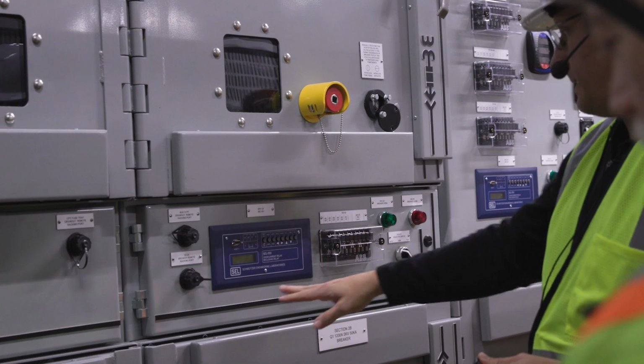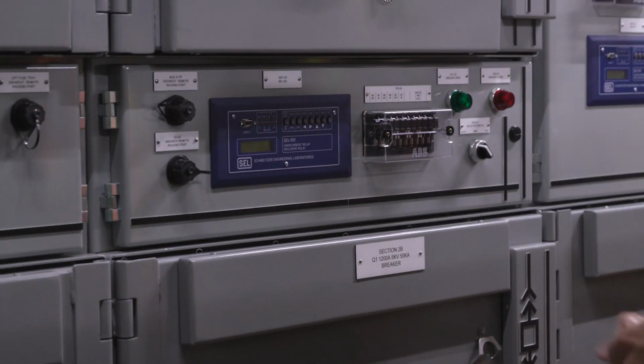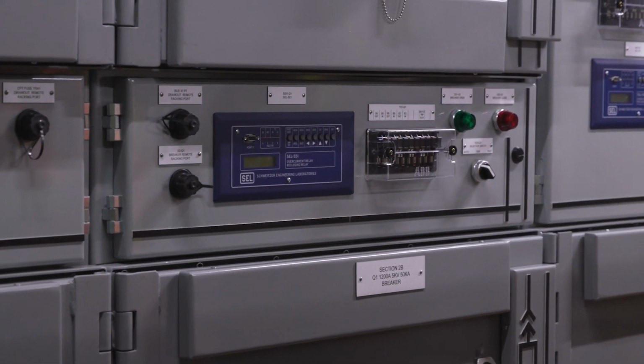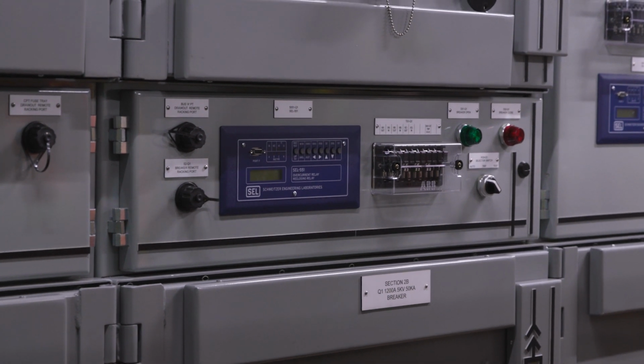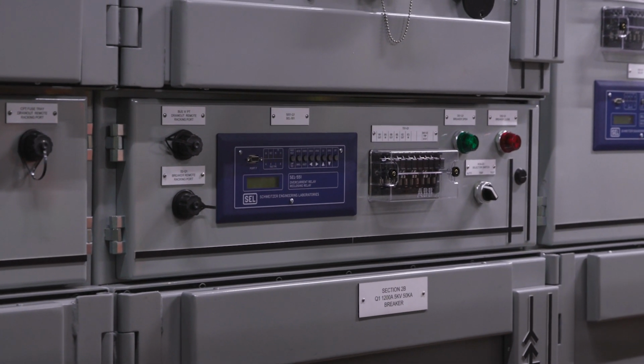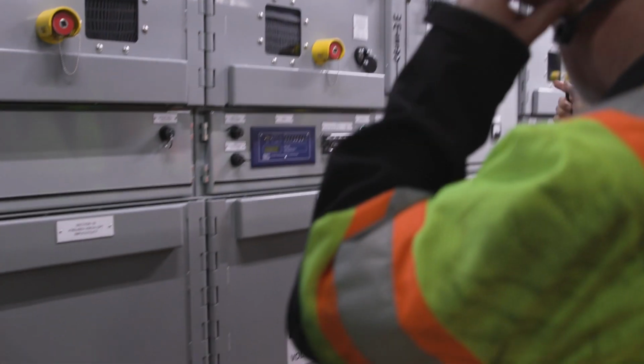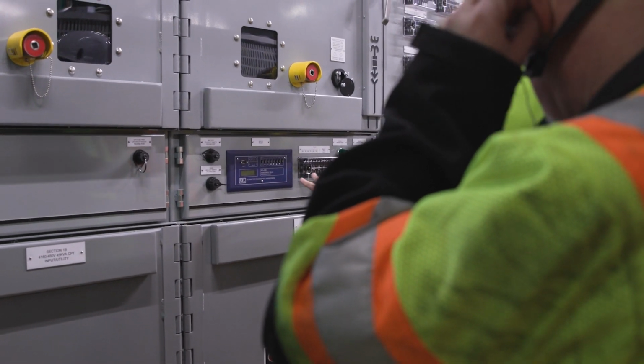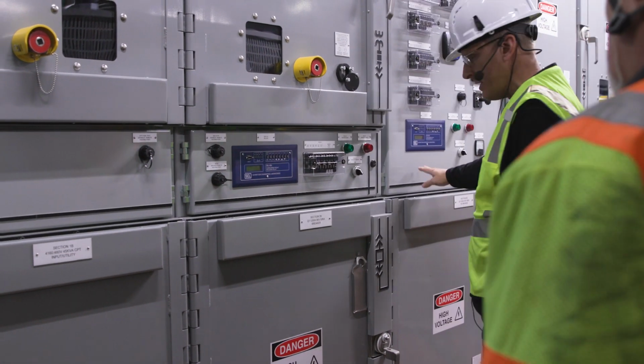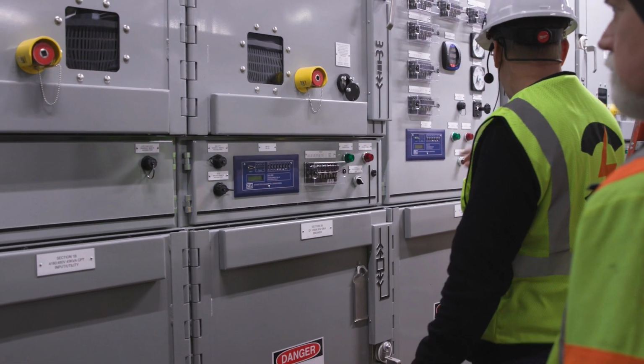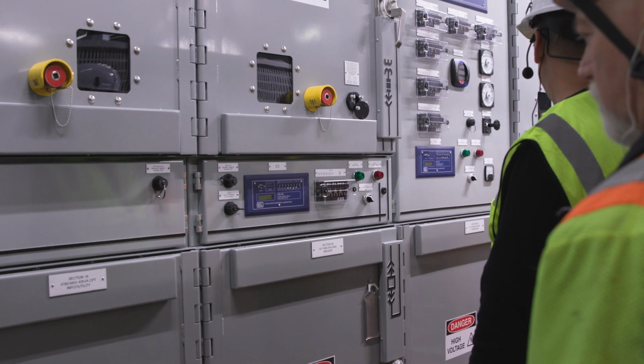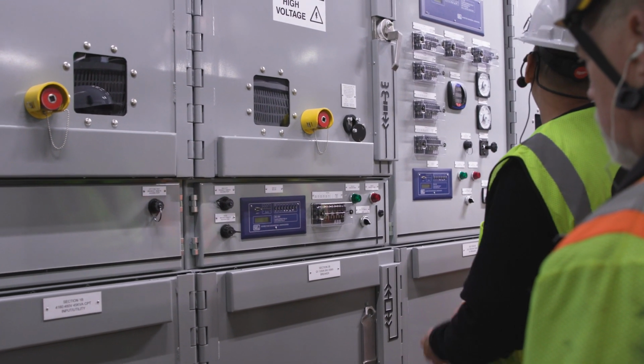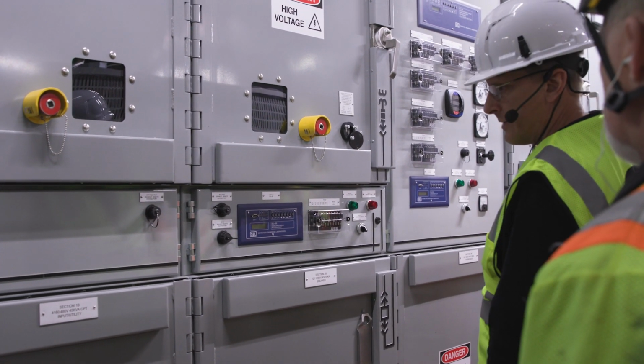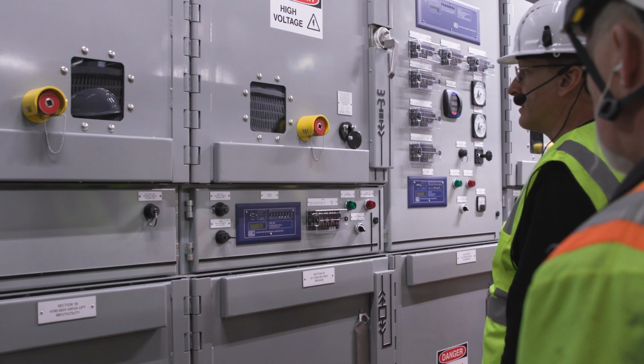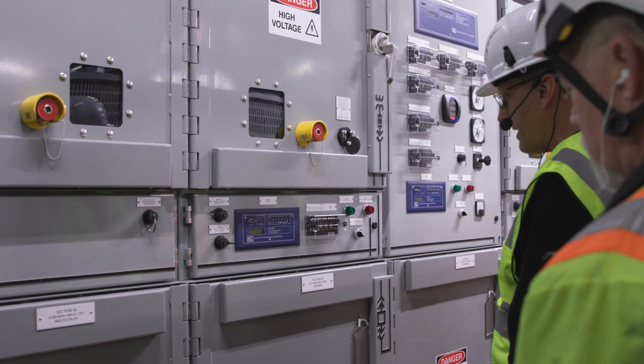Each breaker has a Schweitzer protective relay, 551s for the main breakers. The Q20 breaker actually has a 387 because it's part of the differential zone protection that was set up by Stanley. But we've got the Q1 breaker here. We've got the bypass breaker on section 3 bottom. And then we've got the output breaker Q2 section 4 bottom. And then on the very end is our Q20 breaker, which is feeding our generator transformer panel.